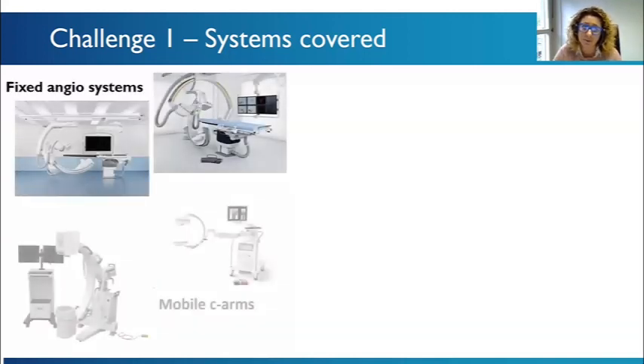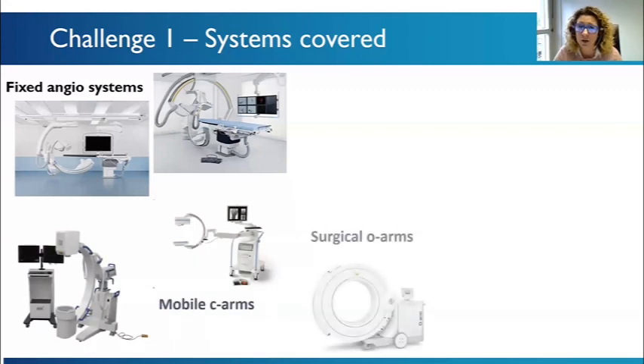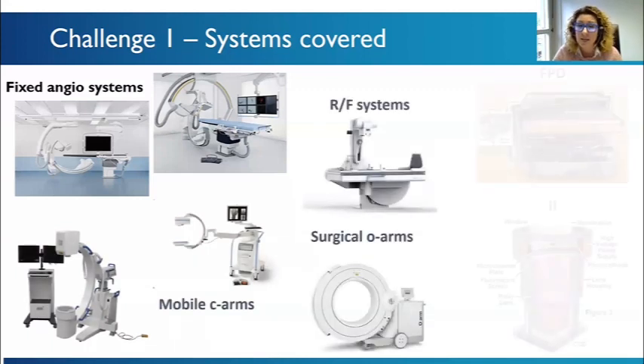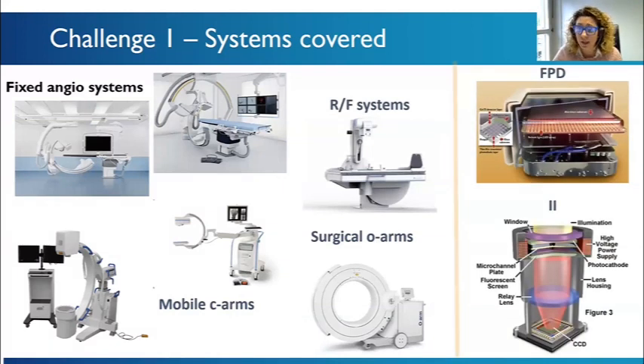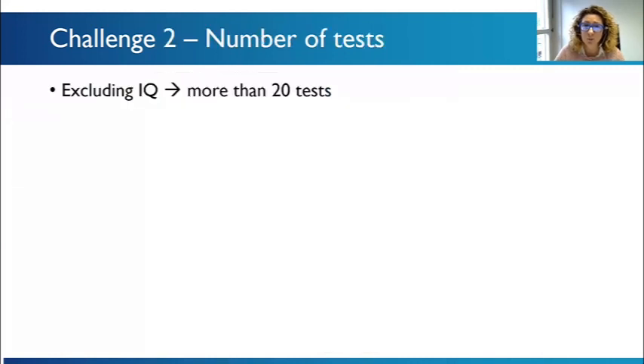During this process, we faced many challenges, and one was which systems should we cover? We say there are fixed systems, there are mobile C-arms, there are surgical o-arms, there are RF systems, there are both flat panel detectors and image intensifiers. So is it possible that one protocol fits all? That was one of the challenges. Another challenge was the number of tests, excluding image quality, which has its own place in the protocol. There are more than 20 tests.